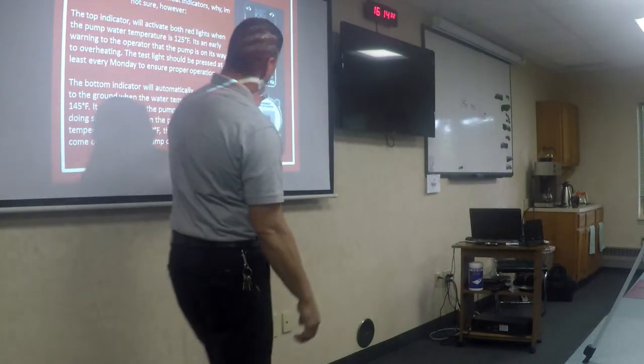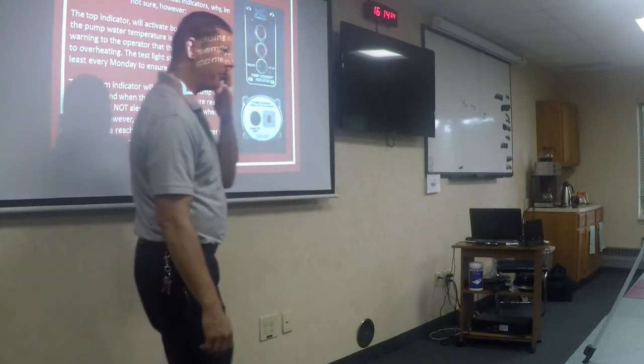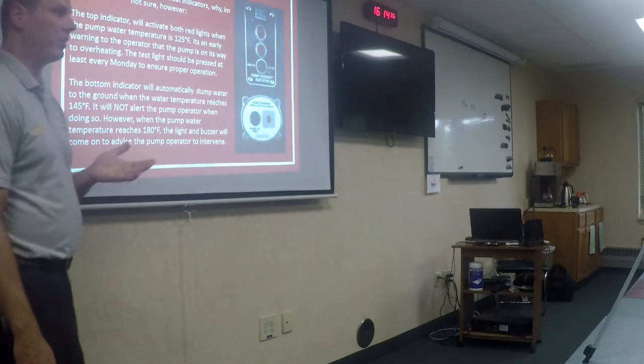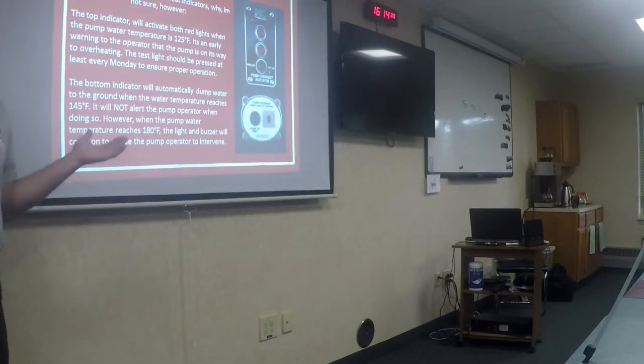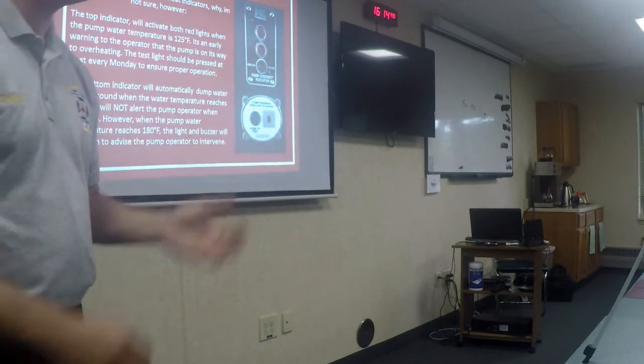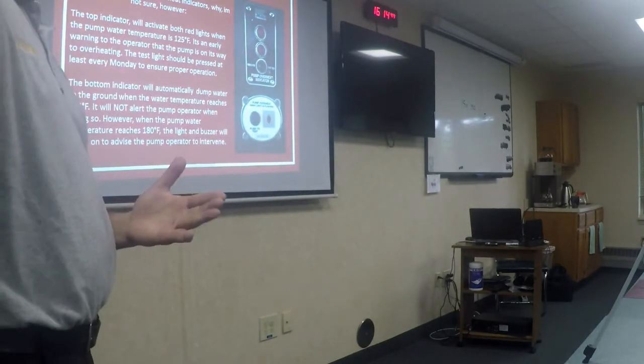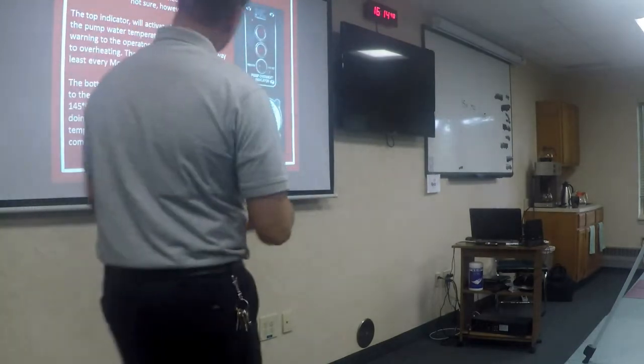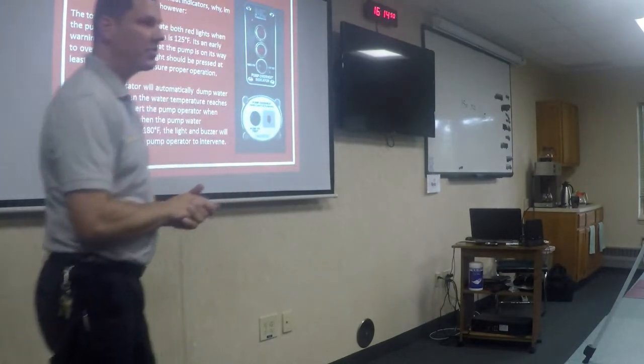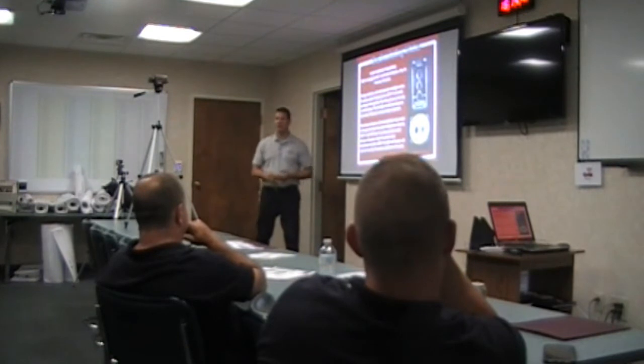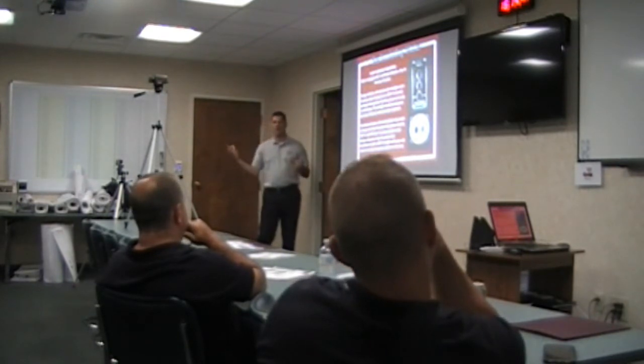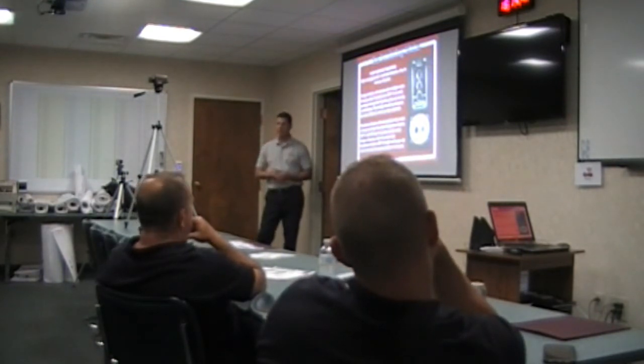This has a test button that should be tested when you're the pump operator on Monday to see if it's working. Personally, I have not tested that light or pressed that button in, I can't tell you how long. I don't know if you guys are doing that regularly. Is anybody doing that regularly? Okay, so it works. All right, so that is that. Just remember, as part of your Monday checks, that button gets pressed and it gets tested.